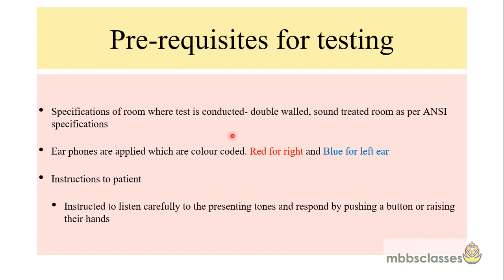Before we understand an audiogram we must know these audiogram legends. There are certain prerequisites for doing audiometry. The room where audiometry is done should be a double-walled, sound-treated room as per ANSI specifications. The earphones used are color coded: red for right ear and blue for left ear. Patients are instructed to listen carefully to the tones and respond either by pushing a button — which generates a flashlight on the audiometer — or by raising their hand.